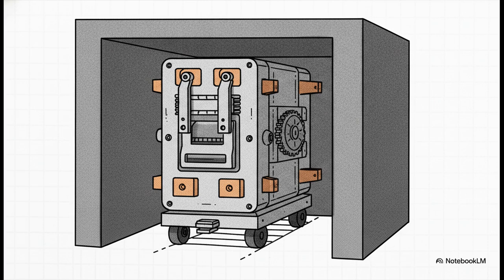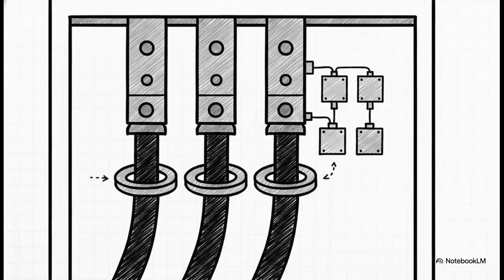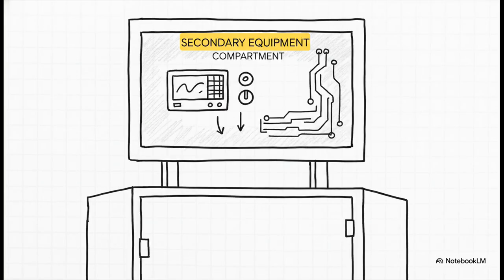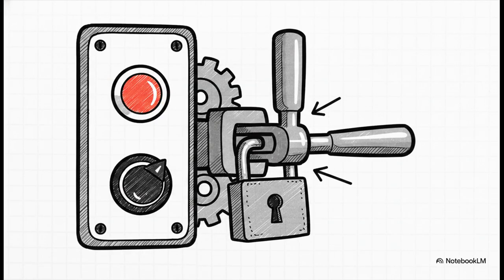Then we have number 2, the circuit breaker compartment, which holds the withdrawable breaker. Moving on to number 3, the cable terminal compartment, bringing in the cables and sensors. Number 4 is the secondary equipment, housing the protection relays up top. And rounding it out is number 5, the operating unit, for manual control and interlocking.